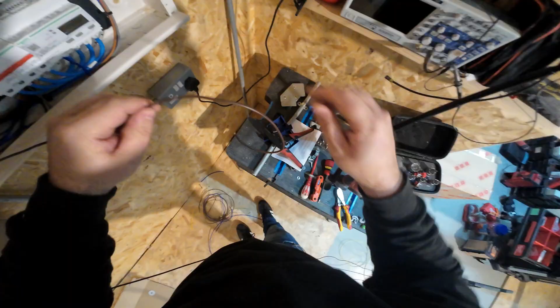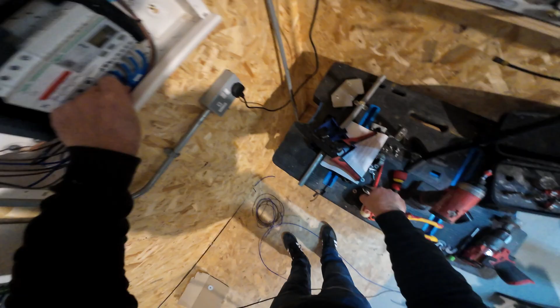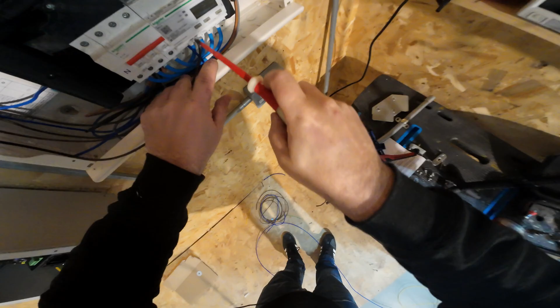Metering kits are pretty common in commercial environments. If you've not seen those, if you work in the domestic sector training to be an electrician, you might not have come across it before. That's how they work. You take your feed into the meter itself, and then it loops off and away to that main switch. And that all comes pre-populated in the metering kit from Schneider. So we just need to pop the inputs in there to power the meter basically.